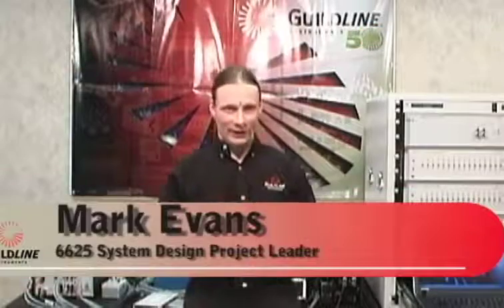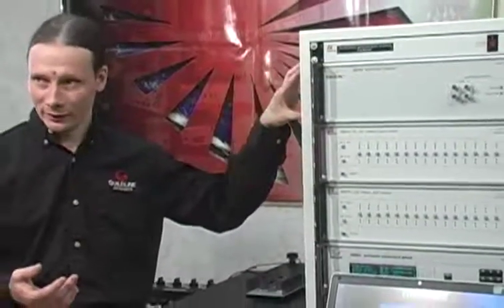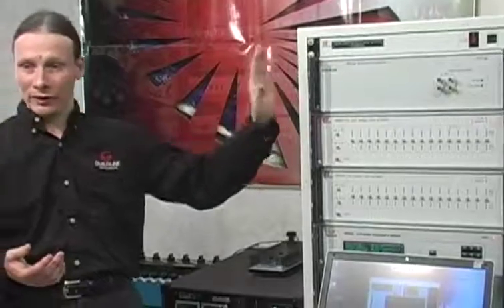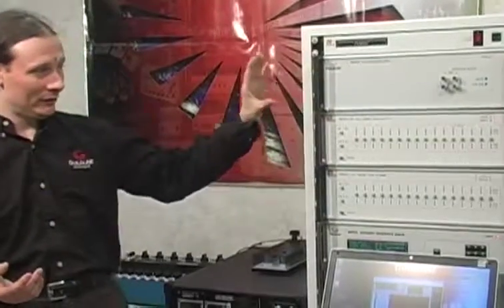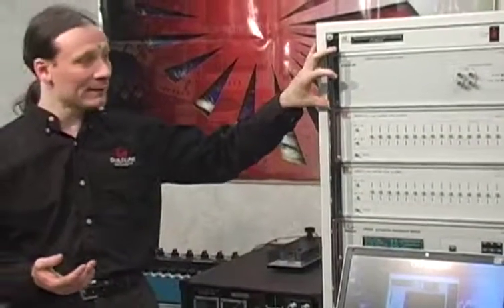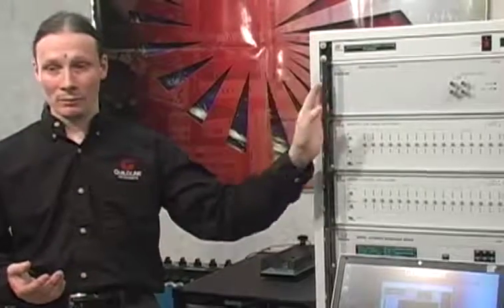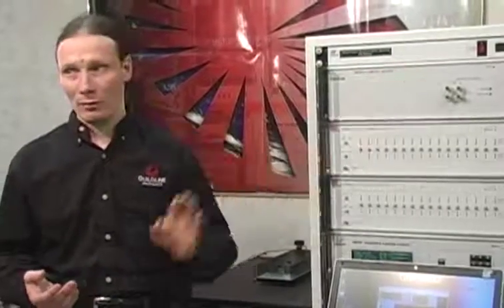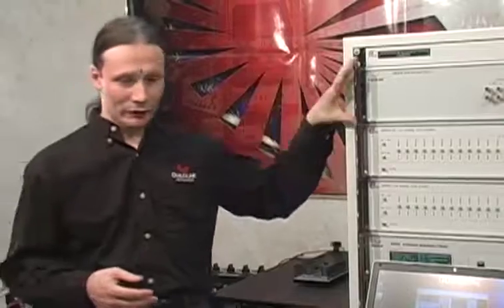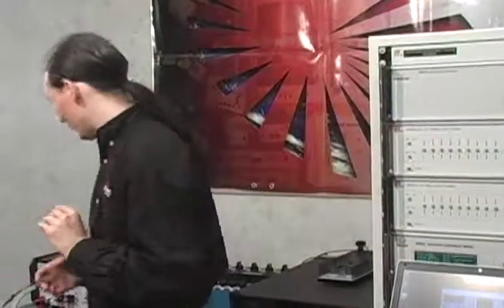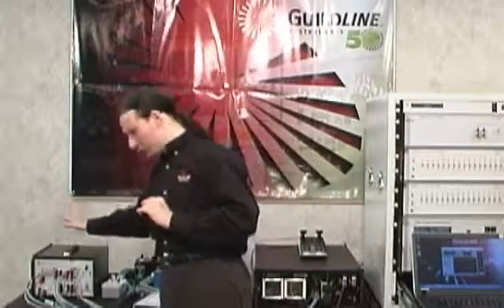We're going to discuss the working set cal. Now the working set cal is a utility that's written in BridgeWorks in the plugins, and this plugin essentially allows you to calibrate the known resistance values against primary reference standards. The known resistance standard, which is your working set, is kept in the top bay here in your rack, and consists of the 1 ohm all the way up to 10 meg and a 0.1 ohm on the end. And this bank of resistors is calibrated against a set of primary references, which is sitting over here.